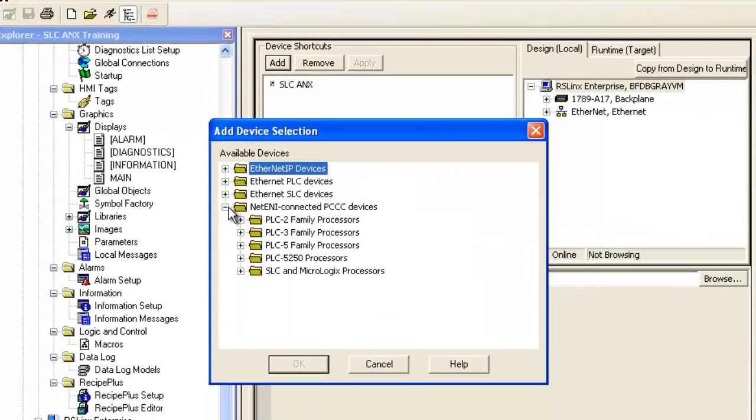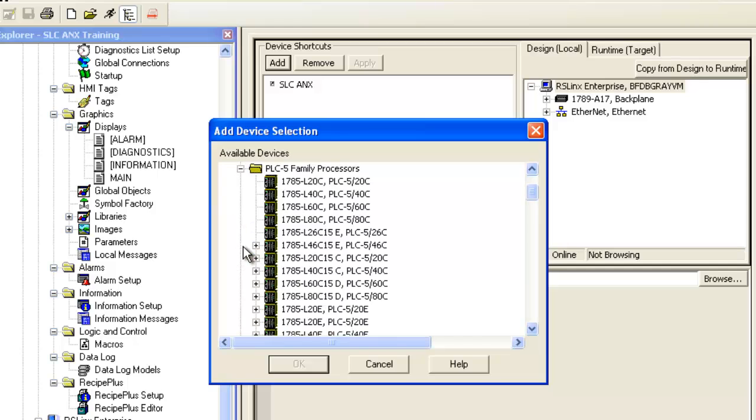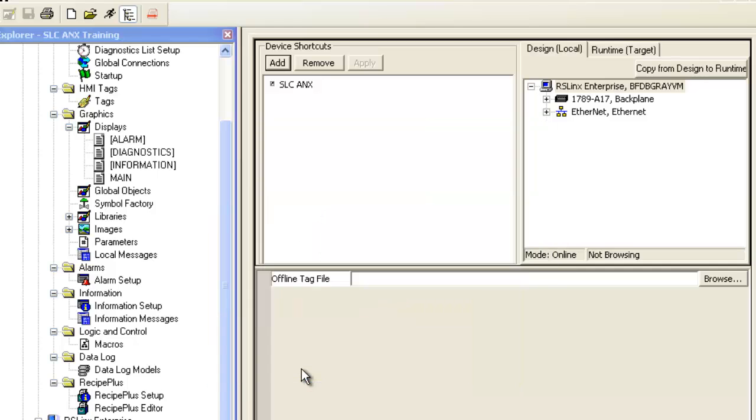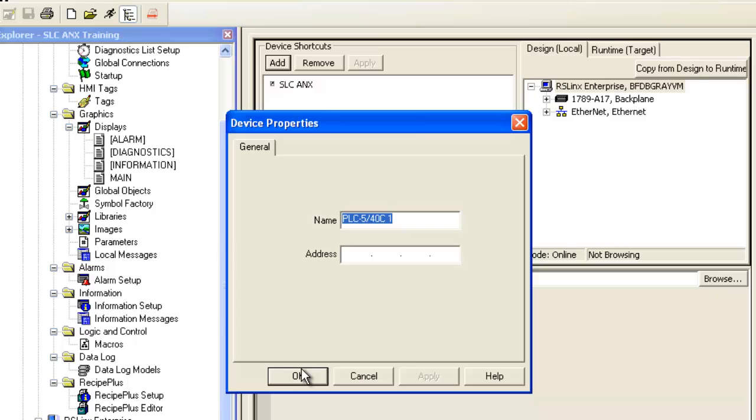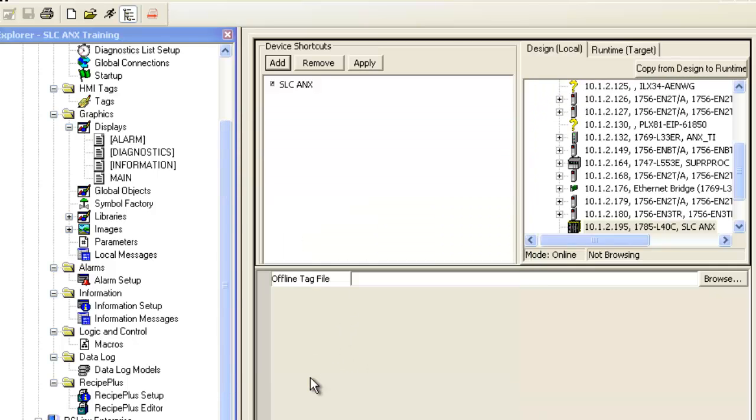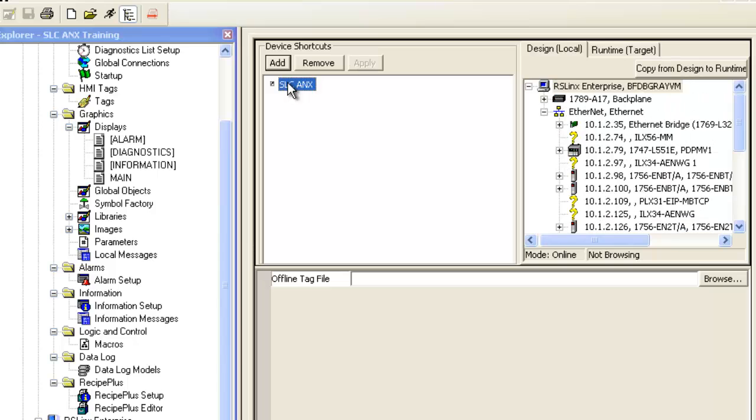Expand the Net ENI option at the bottom, then expand the PLC5 family and select PLC5 40C and hit OK. We'll name the device SLC Annex and then give it the IP address of the Annex module. Select the device we created on the right and the new shortcut that we created and click Apply. This will tie the tag browser to the IP address of the Annex module.